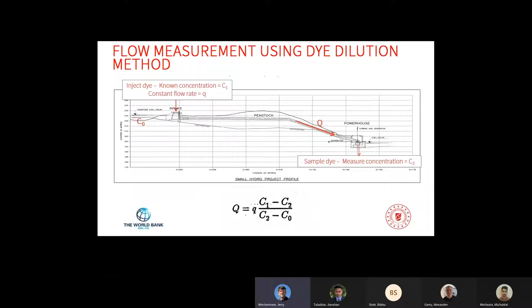Just another couple of photographs. This shows, in the dark purple container here, sitting up on the scale, the injection solution. Just a drop will spread very, very far because it's fluorescent, so we need to be careful not to spill it. And basically we measure the rate of injection using a scale. So you see the figure on the right-hand side showing that straight line. That's made up of several thousand data points, which is basically measuring the weight as a function of time in order to calculate the injection rate.